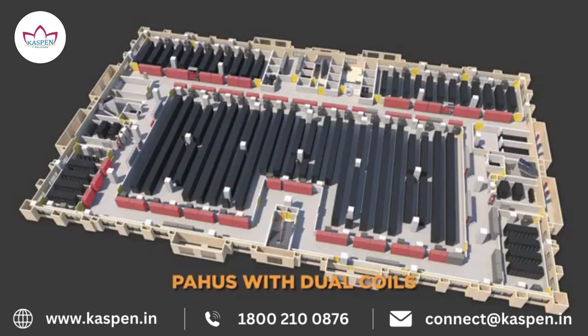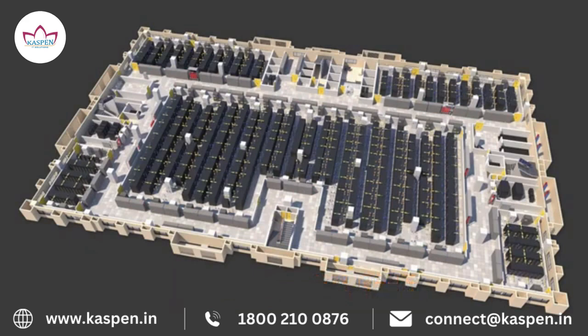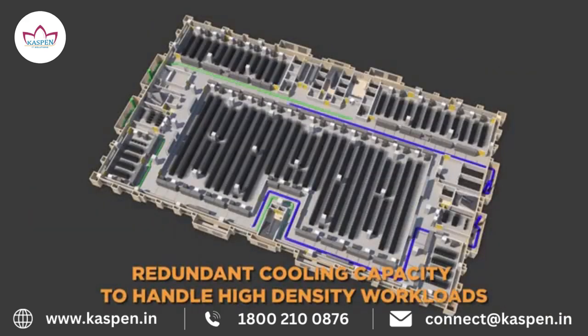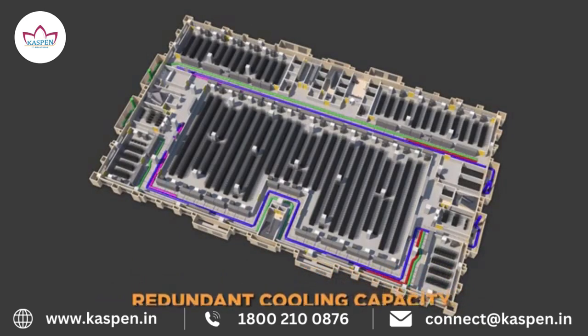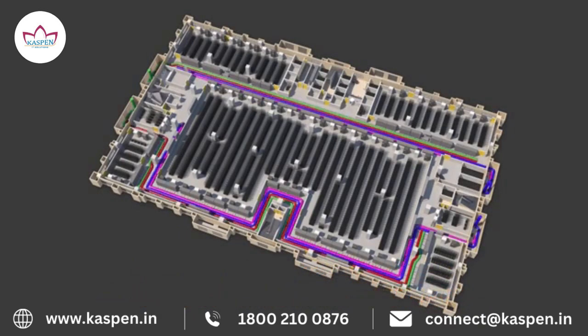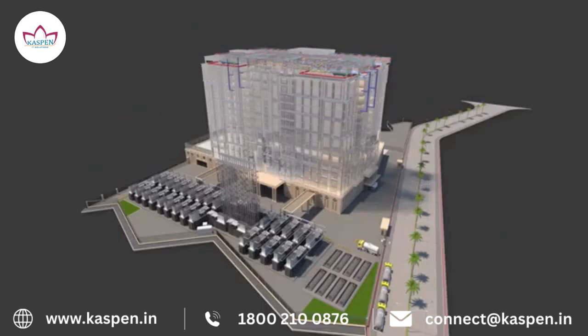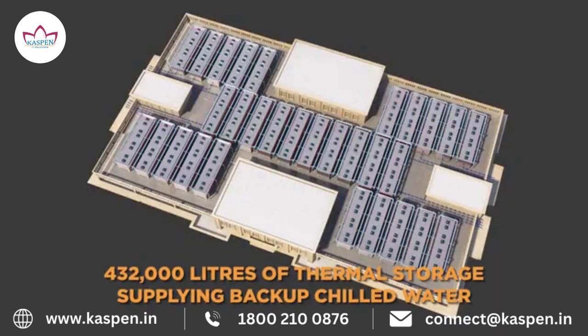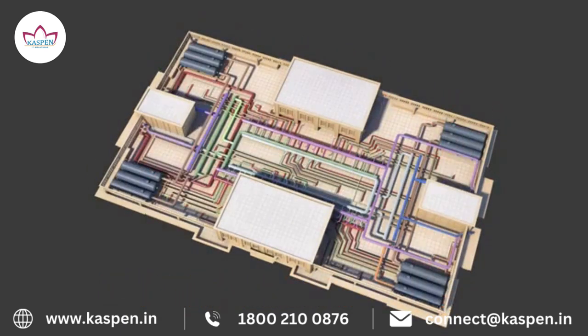Precision air handling units with redundant coils and UPS-powered fans maintain precise cooling and humidity in the server halls. Redundant coils of precision air handling units get chilled water through N+N redundant supply lines and dispose of the hot water through N+N return lines. 34 chillers of 400-ton capacity each supply chilled water to the precision air handling units via dual supply and return header system. In case of a temporary chiller outage, due to changeover in power source from the main feeder to diesel generator and vice versa, the thermal storage tanks continue to supply chilled water through UPS-powered pumps to the precision air handling units, thus ensuring uninterrupted cooling to server halls at all times.